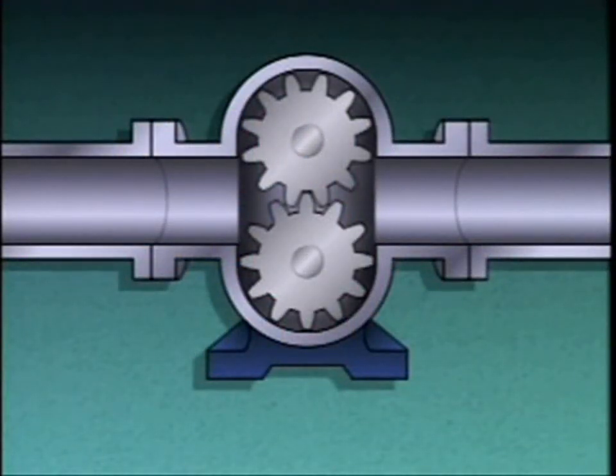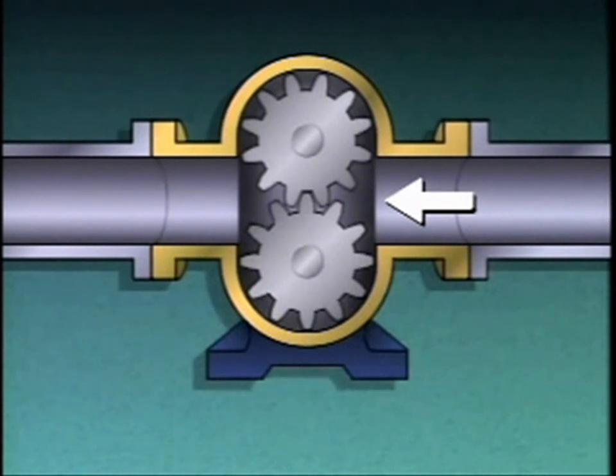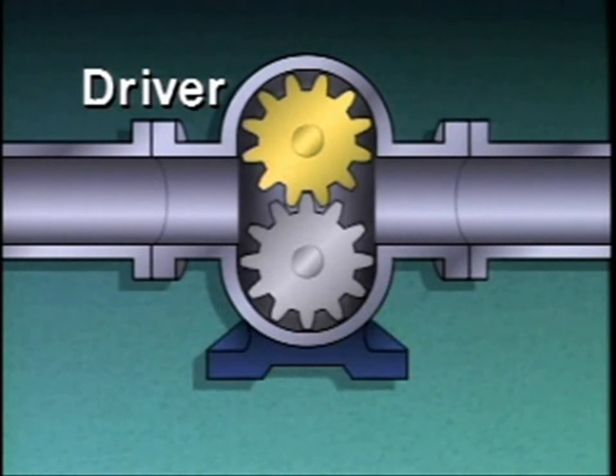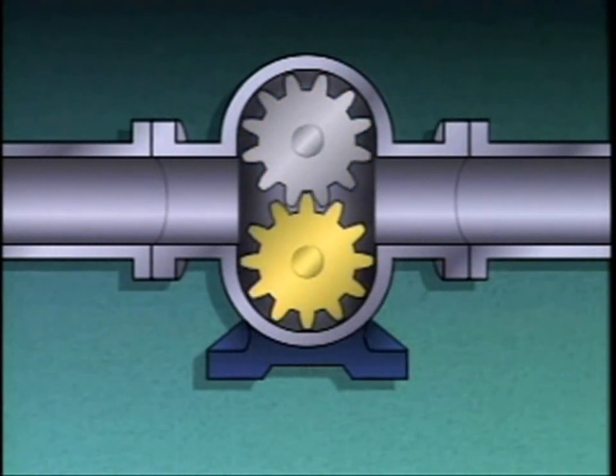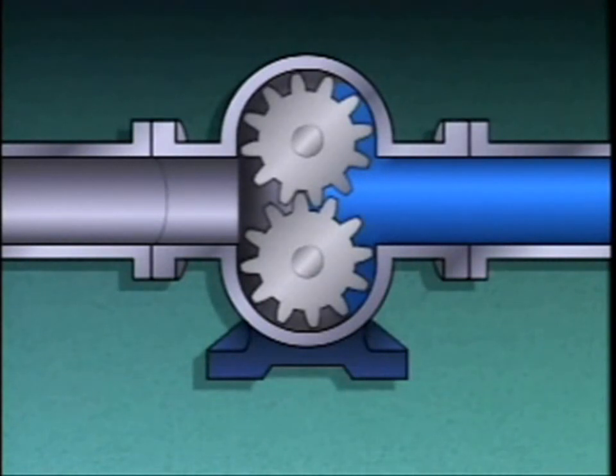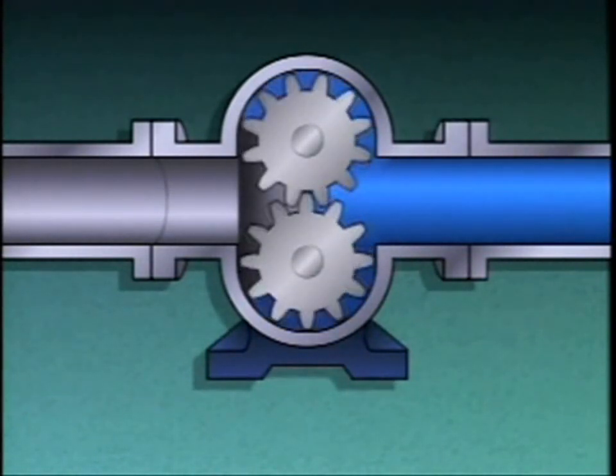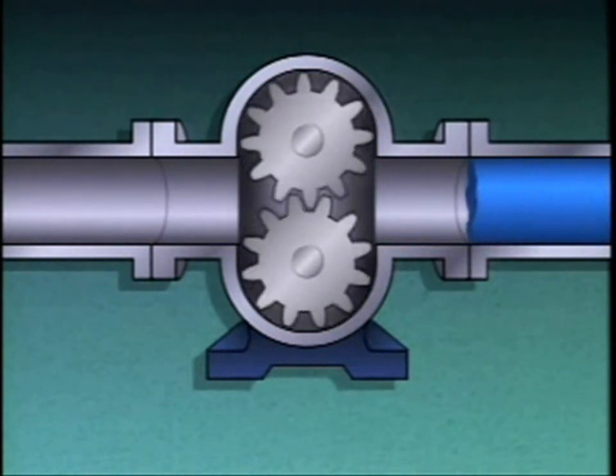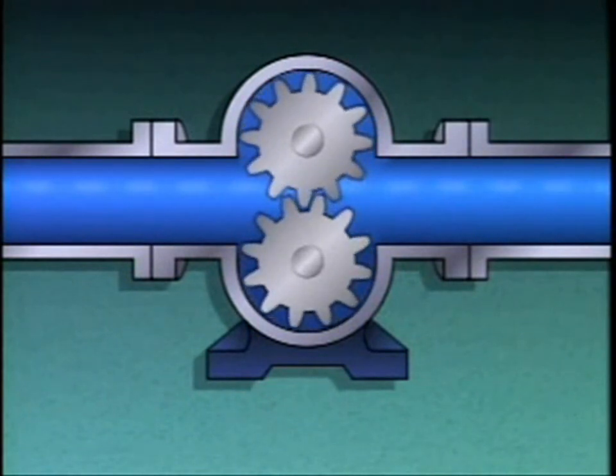One of the more common types of gear pumps is an external gear pump. The external gear pump shown in this illustration consists of a casing with a suction port, a discharge port, and two gears located inside the casing. One gear is rotated by the pump's driver — this gear is often referred to as a power or driver gear. The other gear moves because its teeth are meshed with the teeth of the driver gear; it's called the idler gear. During operation, liquid enters the pump through the suction port. As the gears turn, the liquid is trapped in the spaces between the casing and the gear teeth and moved along the casing. When it reaches the discharge port, it's forced out of the pump. On this type of pump, each space between the gear teeth positively displaces a given amount of liquid, so on each revolution that the gears make, a specific amount of liquid is pumped.